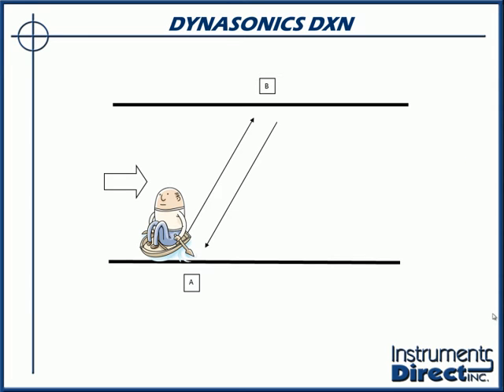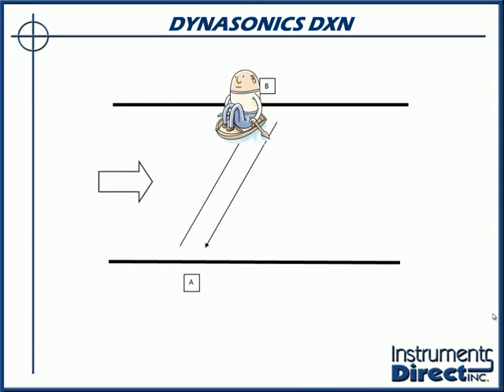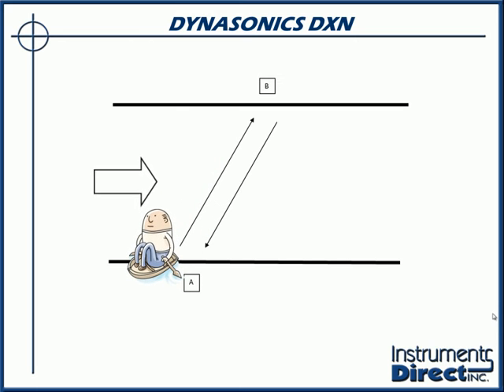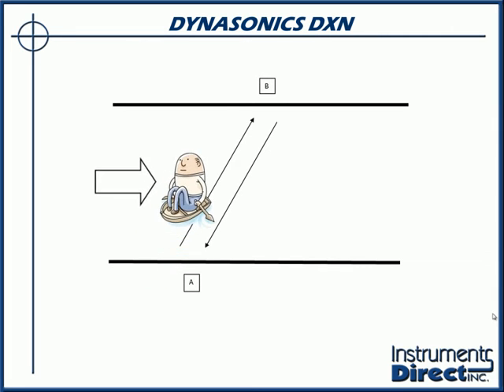Let's look at the ultrasonic transit time flow meter. An ultrasonic transit time flow meter is a unique application, and just listen to the words: ultrasonic transit time. The transit time flow meter analogy is a man in a rowboat who wants to cross this river. He gets in the river and you notice the current's flowing from left to right. Well, this carries him downstream across the river in a certain period of time. But when he comes back across the river, he has to come against the current. It takes him a longer period of time to transit across the river. So the differential between when he went across and when he came back, that differential is the coefficient we use to derive how fast the river's going.